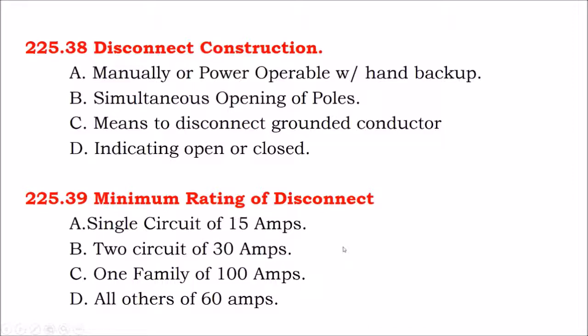And then there are some minimum ratings for the smallest disconnect size requirements. And this one's interesting. On a single circuit, you've got 15 amps. Single family home, there's a minimum 100 amp mandate. So you can design a house and only specify a 100 amp service panel if you want to, assuming that the other parts of code that we talked about before are met, square footage being one of them, or you do a calculated load test. And then we get to the all others of 60 amps. And what we'll see later on is that for supply side connections, they're really looking for a 60 amp connection on supply side, as far as the minimum cable gauge and rating for that supply side connection.